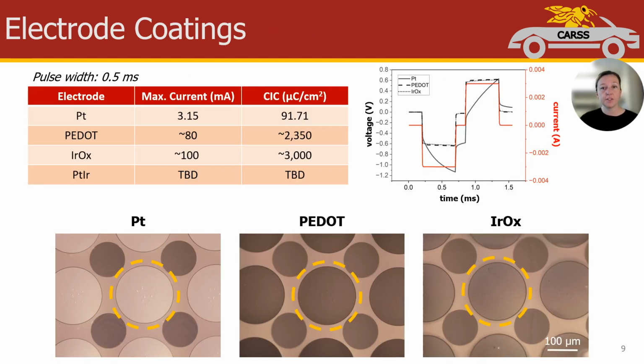For the stimulation use case, the charge injection capacity, or CIC, is a crucial indicator of device performance in vivo, as it tells us the maximum current we can safely apply during stimulation without damaging the electrodes. The CIC is measured using voltage transient measurements, in which a current pulse is injected and the resulting voltage response of the electrode is measured. This is represented in the graph in the top right corner, where we can see the input square current pulse in red and the resulting voltage in black for different electrode surfaces. In other terms, this test looks at the polarization of the electrode system in response to charge injection.